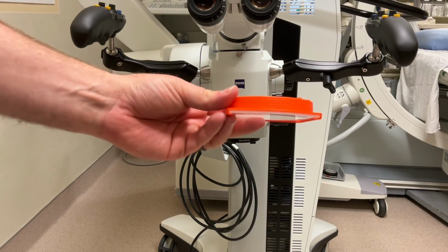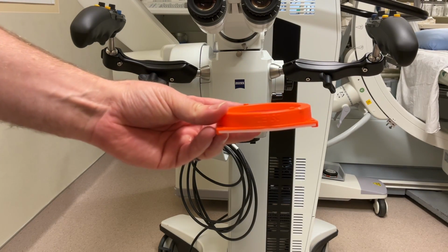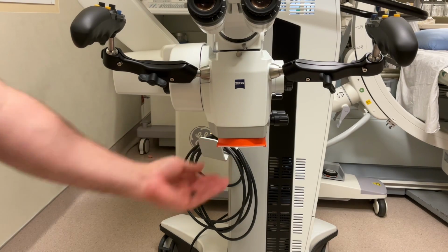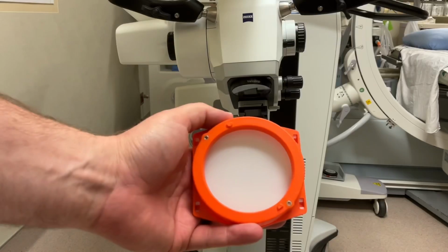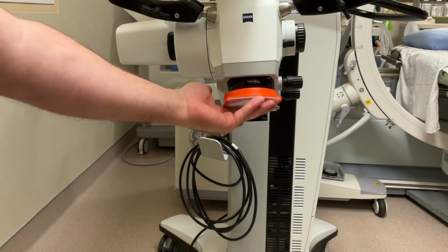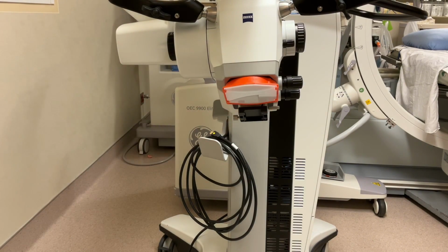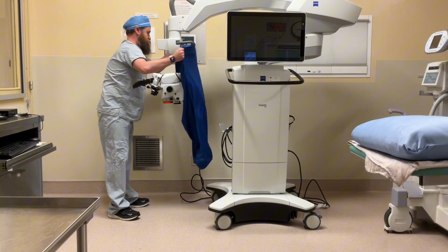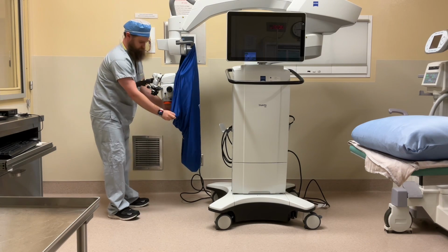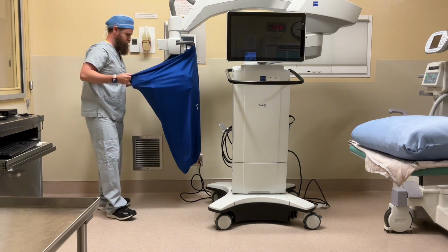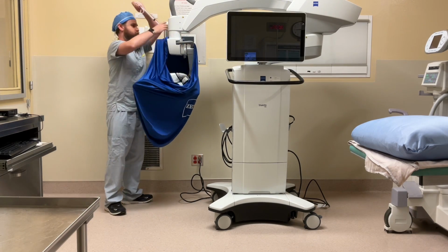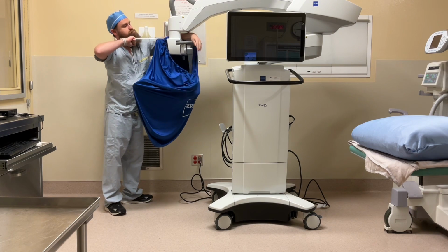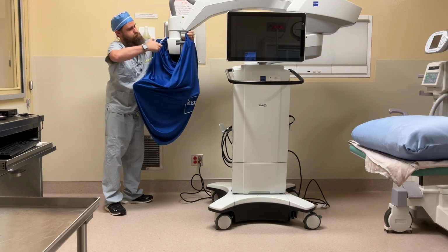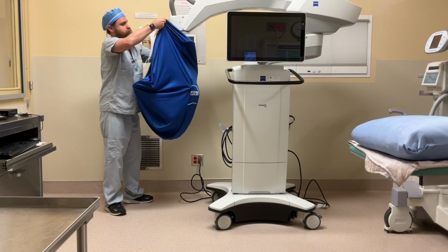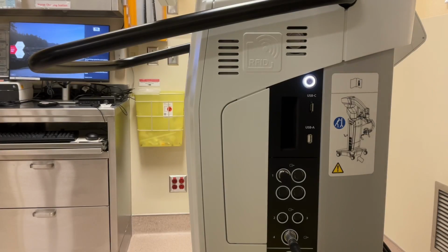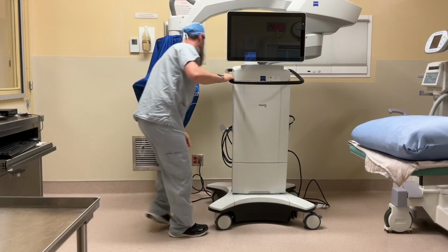Take the lens cover and place it on the varioscope. The lens cover is embossed with Zeiss and should line up with the Zeiss logo on the microscope. The cover has magnets that only line up one way with the microscope. Cover the microscope head with the Zeiss dust cover bag. When the power button is turned white, the shutdown procedure is finished and the microscope can now be unplugged.